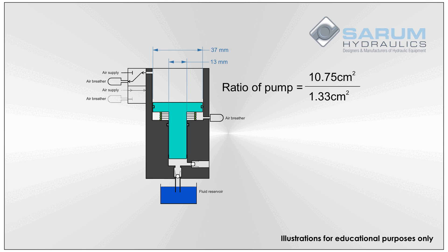This results in our example pump having a ratio of around 8 to 1. This means if you were to feed in 5 bar of air pressure on the top, you would get 40 bar of hydraulic pressure on the bottom.